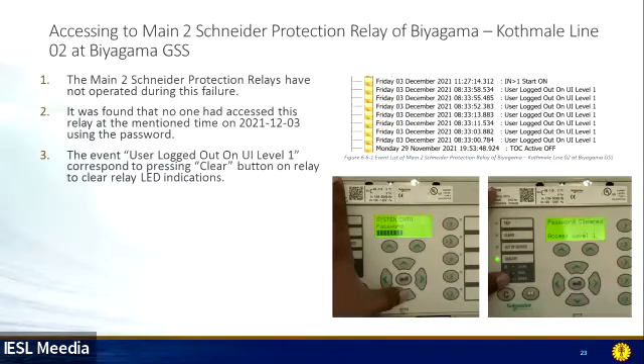Because of this, we forwarded this information to the relay manufacturer and asked them to explain why there were 7 logout events within a 1 minute time period. This happened in the early morning of the total failure day, around 8:33 hours. So that's a very critical issue.